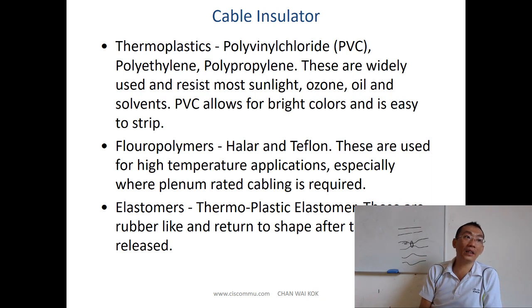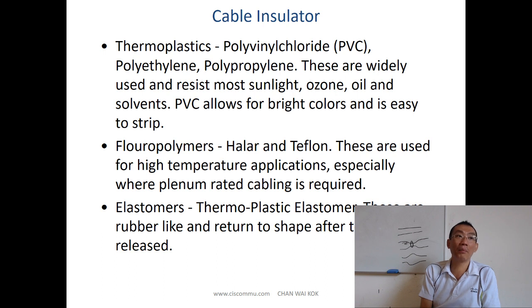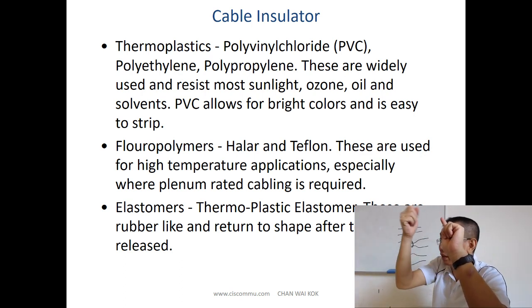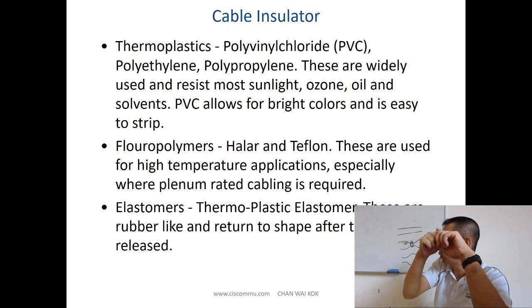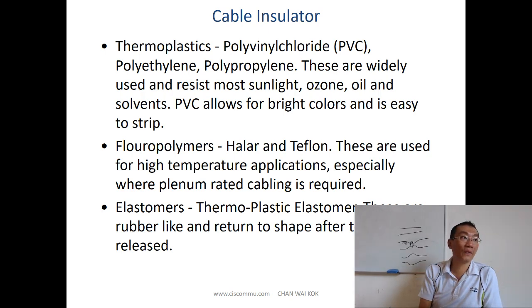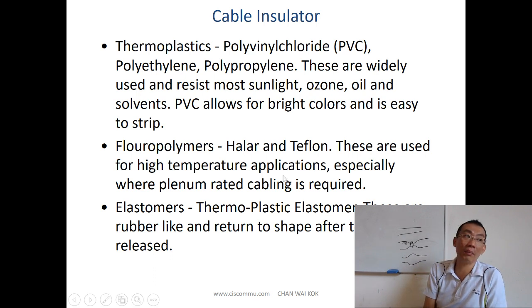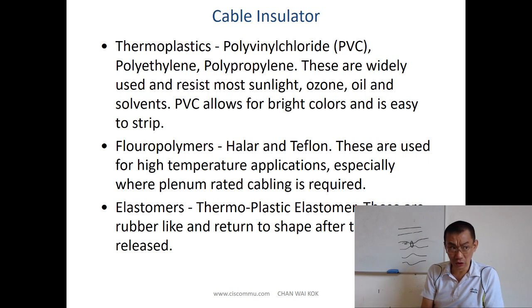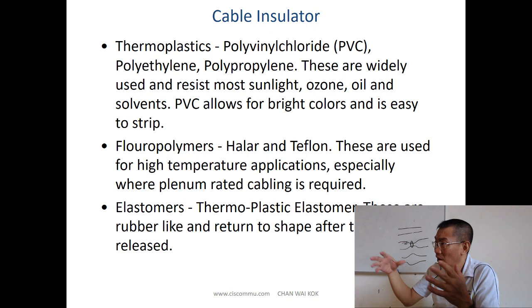The cable insulator types include: thermal plastic, which is widely used and resistant against sunlight, ozone, oil, and solvent; PVC, which allows bright color and is easy to strip — meaning you can easily remove the plastic to expose the copper for connections. There is also fluoropolymer, used for high-temperature applications, and elastomer, which is rubber-like and returns to shape after tension is released — used in underground or harsh environments.